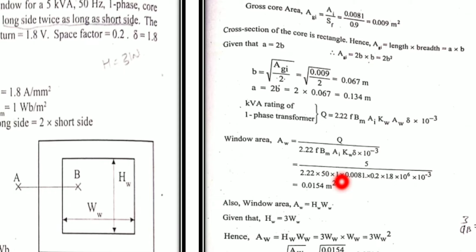Then what we need to do now is substitute all the values. Q is the kVA rating, how much is it? 5 kVA. 5 divided by 2.22, frequency is 50, maximum flux density is 1 Weber per meter square, AI we got as 0.0081, window space factor is 0.2 as given, and delta, the current density, is given as 1.8 ampere per millimeter square into 10 raised to minus 3.